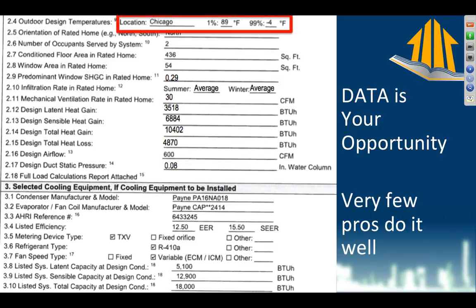First, Chicago - this is how it's all supposed to work. Chicago has a 1% and a 99% design temperature. That means the 1% hottest day we'll reach is 89 degrees Fahrenheit, and the 99% coldest day we'll hit is -4 degrees. This is based on weather stations, so you want to pick a weather station that makes sense for the site where you're building the home, and select these two values.